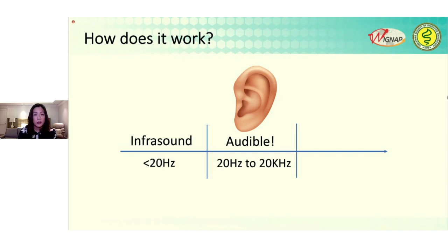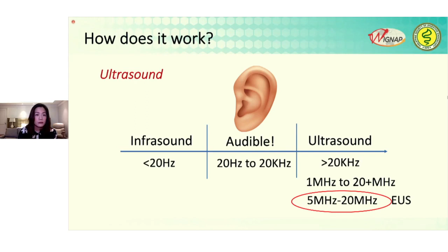But EUS utilizes the high ultrasound frequencies, like 5 to 20 megahertz, 7.5 megahertz being the most frequently used. And this generates a high resolution image in the near field, of course, with limited penetration depth, ranging maybe from 1 to 2 to 5 to 6 centimeters, depending on the ultrasound frequency that is used.